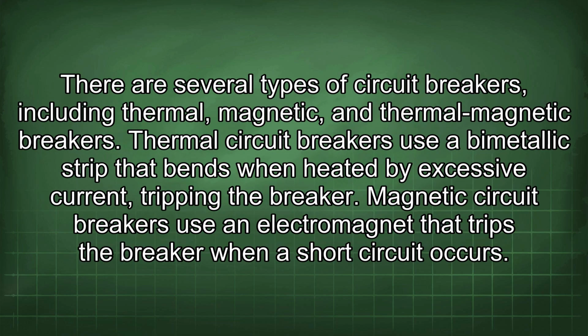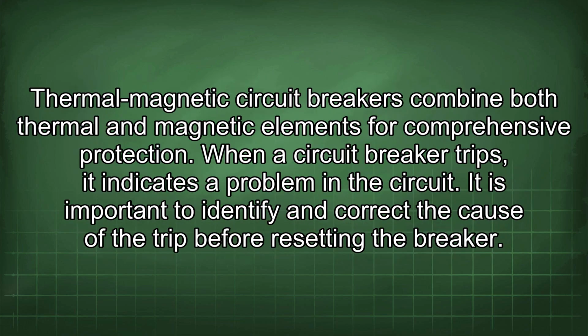There are several types of circuit breakers, including thermal, magnetic, and thermal-magnetic breakers. Thermal circuit breakers use a bimetallic strip that bends when heated by excessive current, tripping the breaker. Magnetic circuit breakers use an electromagnet that trips the breaker when a short circuit occurs. Thermal-magnetic circuit breakers combine both thermal and magnetic elements for comprehensive protection.